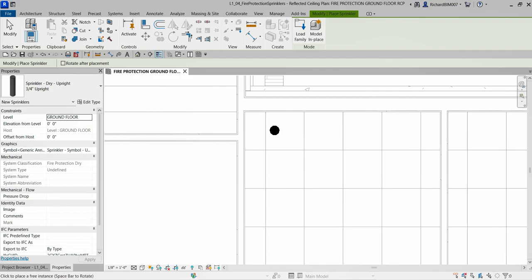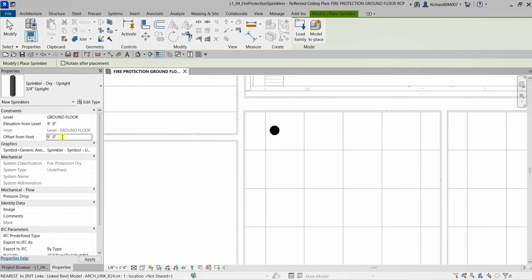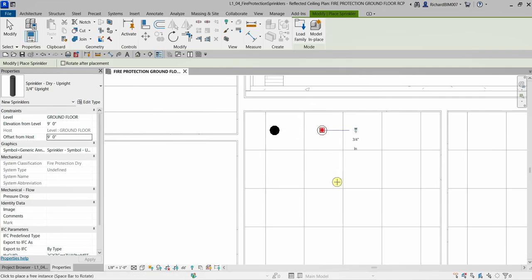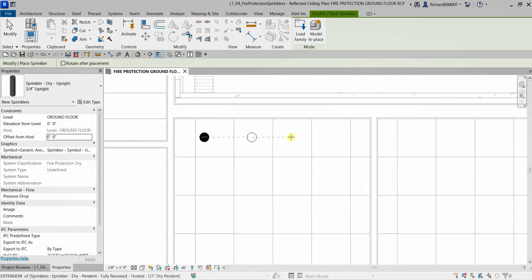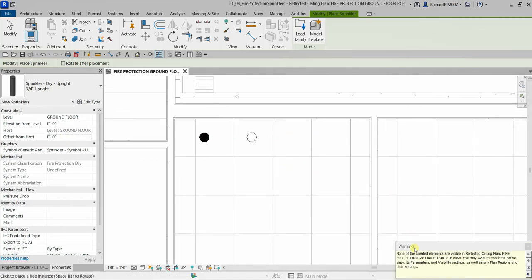Set the offset to nine feet, then place the sprinkler just beside the hosted family. If you forget to change the height and leave the offset at zero, when you click to place it, you'll see a warning: 'None of the created elements are visible.' That means the elevation is zero and you can't see the sprinkler.